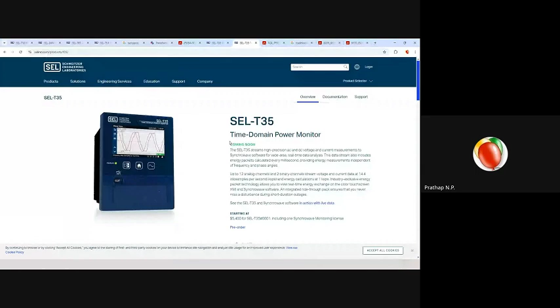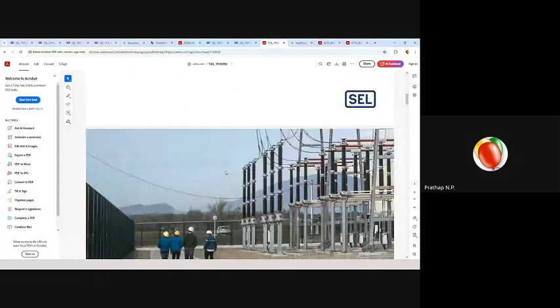I can show one more example. This is equivalent to the IEC 61850 protocol or standard, but it's a proprietary technology called TIDL, time domain link technology. Going back to that drawing, in a normal substation you have CT and PT, with 3-phase coming in as ABC and neutral, and 3-phase going out as ABC and neutral. That's 8 control cables coming from just one CT and PT. You'd also want CTs measured for these relays, these feeders.